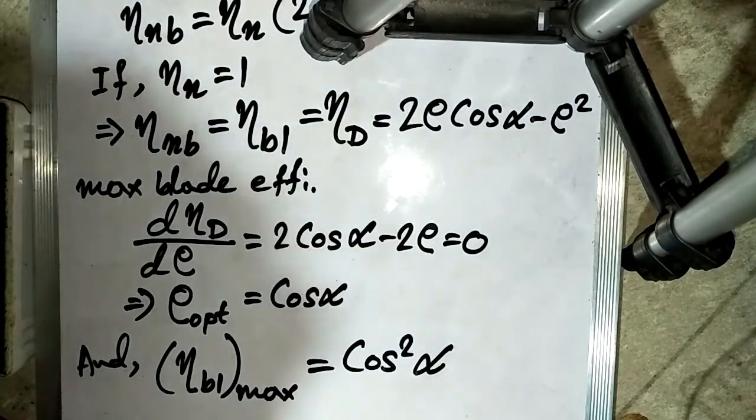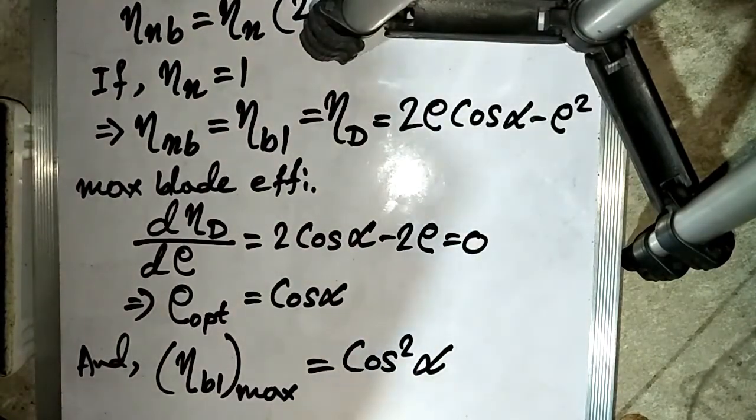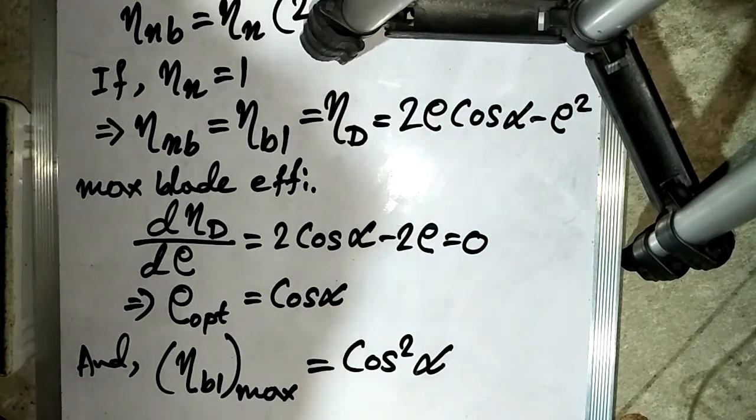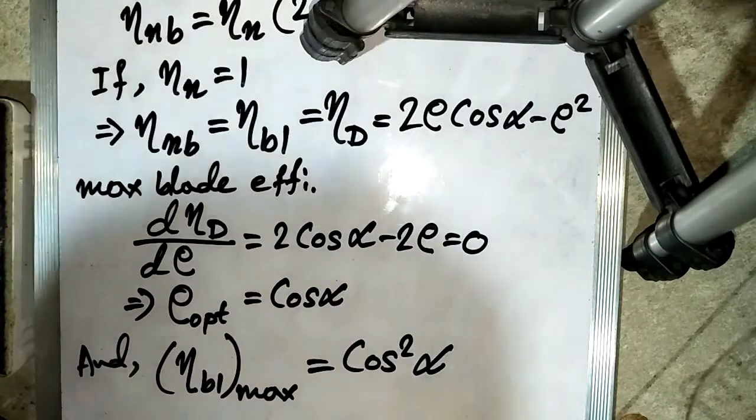In comparison of simple impulse stages and reaction stages, we can say that all the efficiency values are equal. However, when the friction is taken into account, the reaction stage is found to be most efficient, followed by the Curtis and the simple impulse staging in that order, and the friction losses are less significant in the reaction stage since the flow velocities are lower.